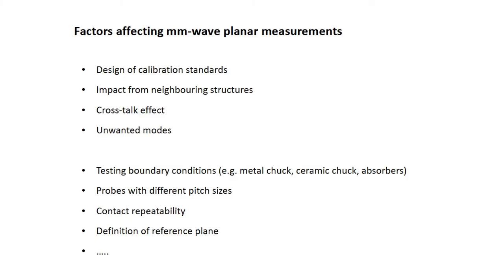On this slide I have listed some factors: design of calibration standards, impact from neighboring structures, cross-talk effects and unwanted mode propagation. There are also other factors like testing boundary conditions — the previous speaker has partially written a paper on this — and probes with different pitch size, because CPW structures can accommodate probes with different pitch sizes. However, results from probes with different pitch sizes at the same frequency range can differ at millimeter-wave frequencies. Contact repeatability and definition of reference plane are also important. Due to time limitations I will only show the impact from four of these factors.